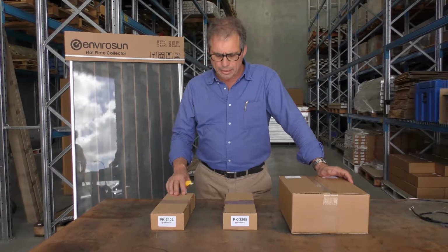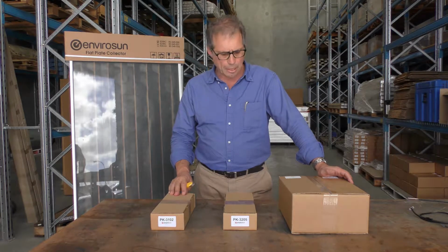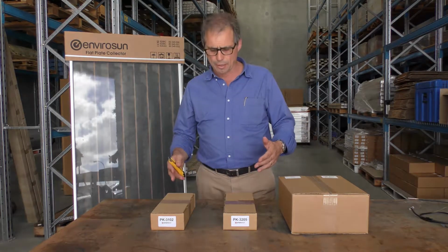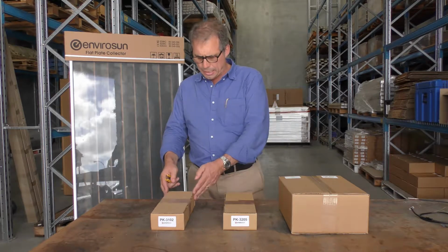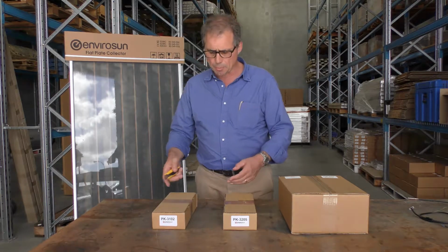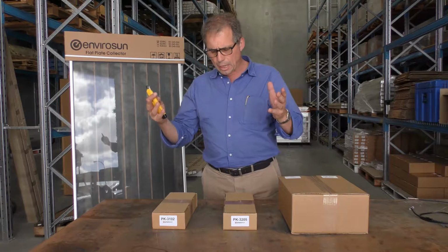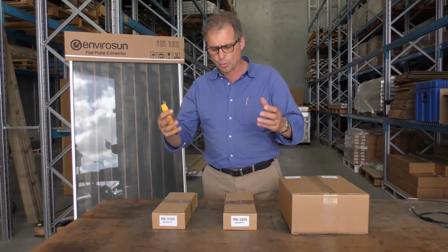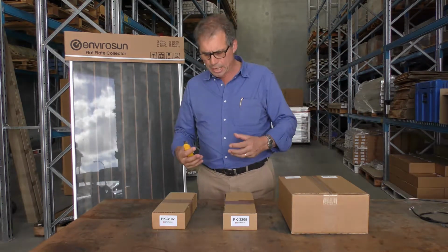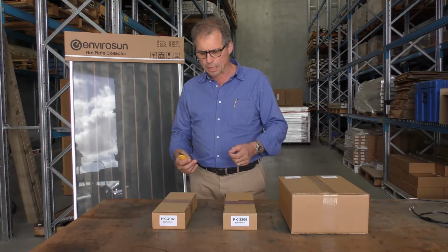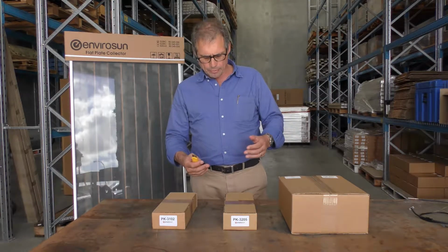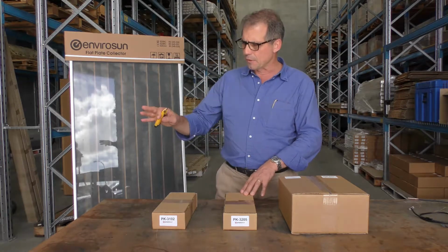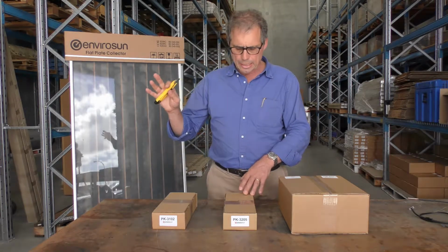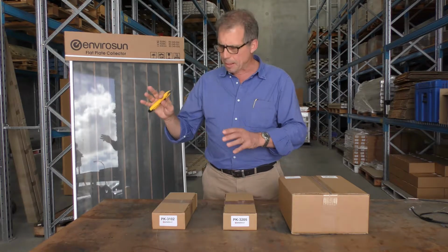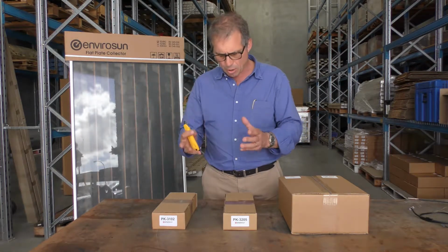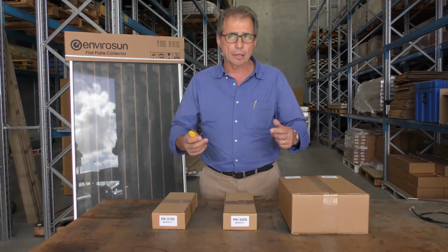Apart from the tank and the collectors that we supply, the other components that you will receive when you purchase one of our AS systems is a roof connection kit, which is a component that we use for all the connections of the collectors together on the roof and the connection to the collectors. I'm going to open those up in a minute and go through it and explain a little bit more about it. Then we have a ground connection kit. This is the kit that we use to connect the pump box and the pump station onto the tank, and these items are, as they say, the ground connection kit.